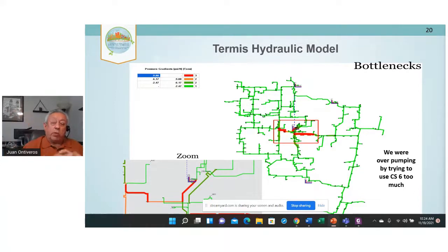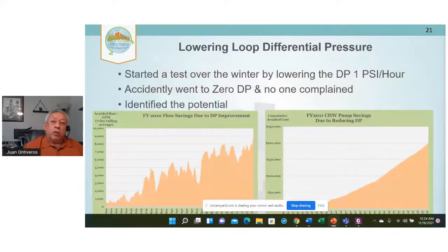So our objective was to lower the pressure. Over a winter, we decided to test how low we could take the pumping pressure. We started lowering our delta P 1 psi an hour, lower and lower. Every hour we lowered another psi. And what happened is we actually went to 0 delta P. In other words, the supply water pressure and return water pressure differential was 0. And no one complained. None of the buildings had any issues. So it showed us that we did have an opportunity by lowering the pressure. This first chart that you see here is 2010. What we learned is we actually saved almost 9,000 gallons per minute by just lowering the pressure.